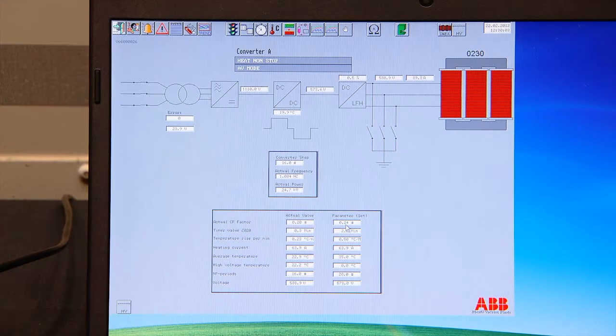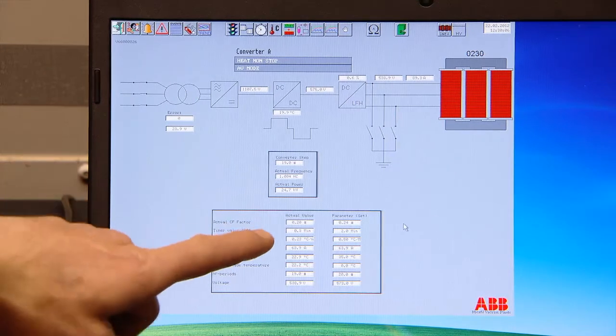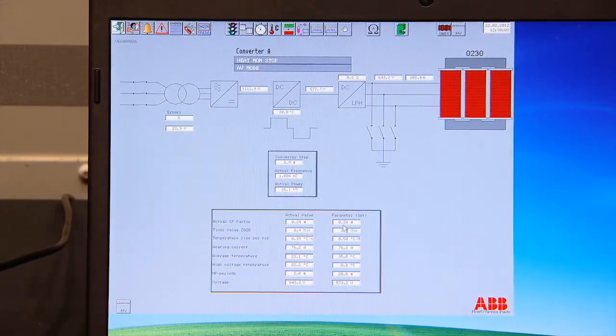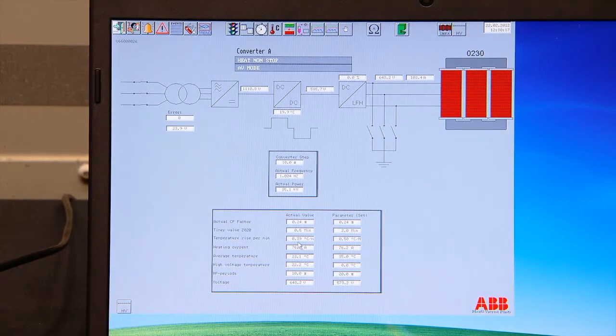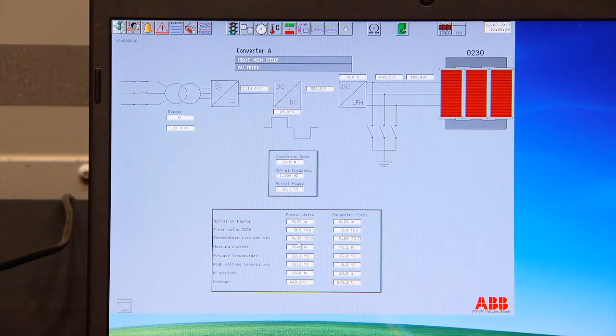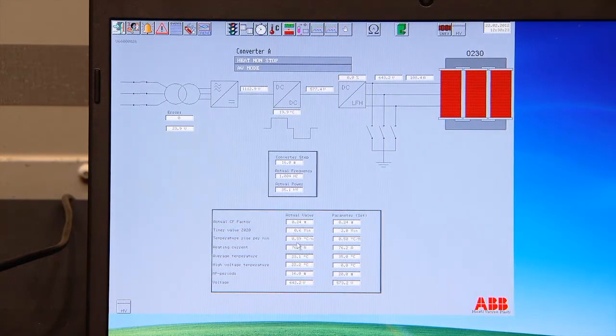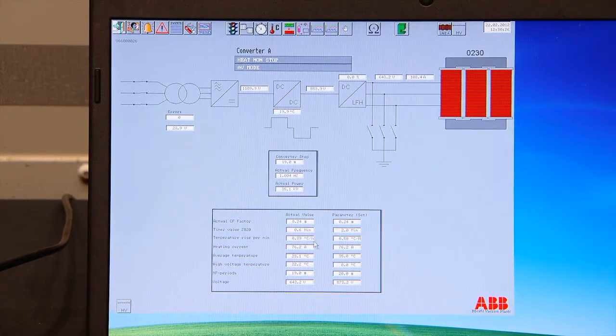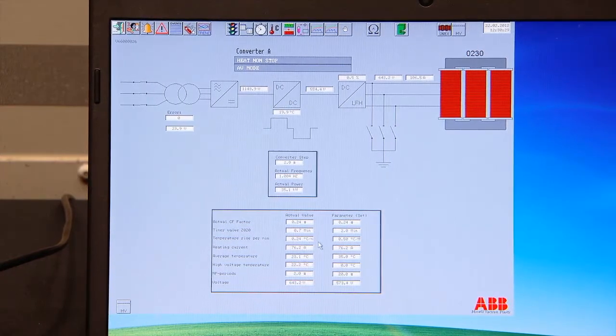So that'll do it automatically? That's automatically done, up to until it achieves 0.5. Up to 0.5, yes. It'll go up by that increment until it achieves that, right? Yes. Okay. So now after 2 minutes he will evaluate again. We are at the moment 0.4 degrees per minute. If this stays like this, we don't know yet, because again, I've seen that fluctuate. Yes, it goes high up and then goes up and down a little bit, yes. It was 0.39, now it's 0.24. That's why we're not reacting immediately on each temperature variation. So you have that 2 minutes for stabilizing.